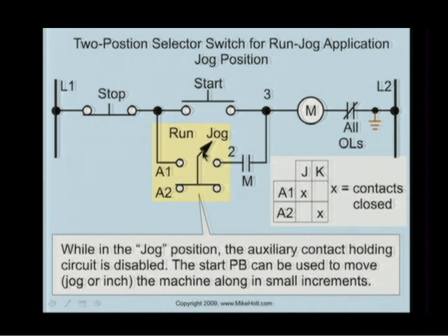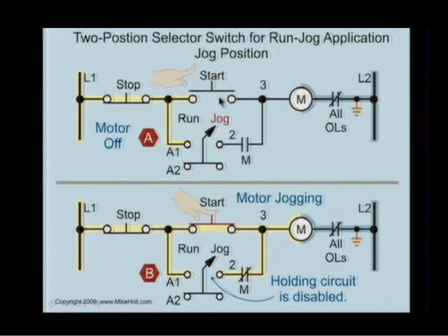Well, in the jog position, the A2 contacts are closed, but the A1 contacts are open. Now, you take your start button, and when you press the start button, do I have a sequence here? While I'm pressing the start button, I'm energizing the M coil and the motor, of course, the contacts are being closed. But the moment that I release the start button, because I cannot maintain the interlock or the latching contact here, because I've opened it in the jog mode, this motor could only run when I press the start button, but the moment I release it, the motor stops. So you just kind of tap it.